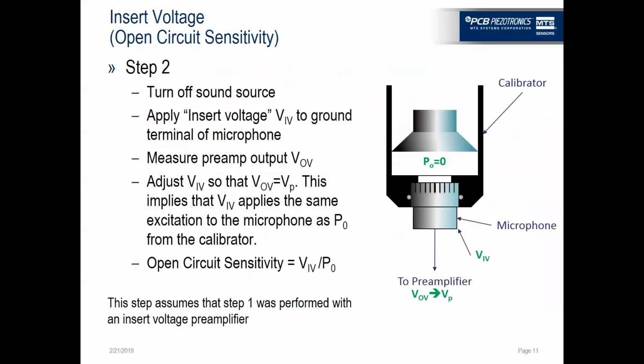So what we do is we will actually take the microphone, and we have a special preamplifier that we can use called an insert voltage preamplifier. And what that does is it allows us to apply a voltage to the electrical terminals of the microphone and then measure the output of that preamplifier due to that input. And once we have it matched, the output to the input of the previous measurement, we can calculate out the open circuit sensitivity of the microphone.